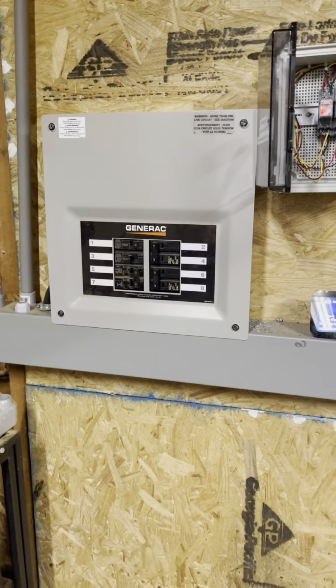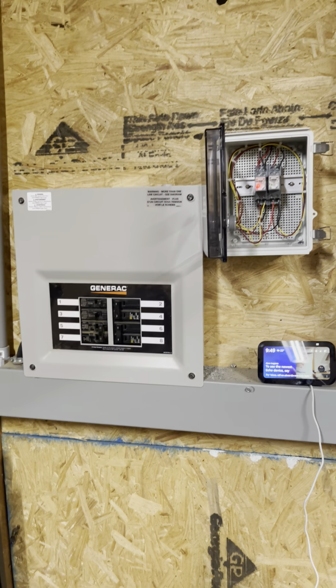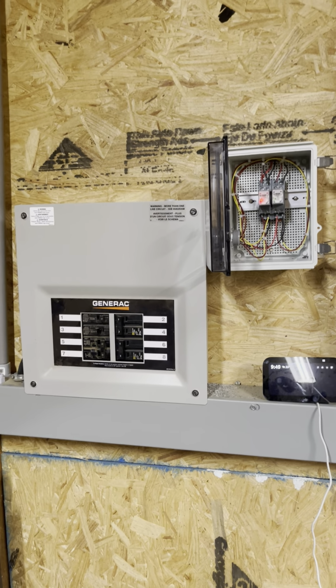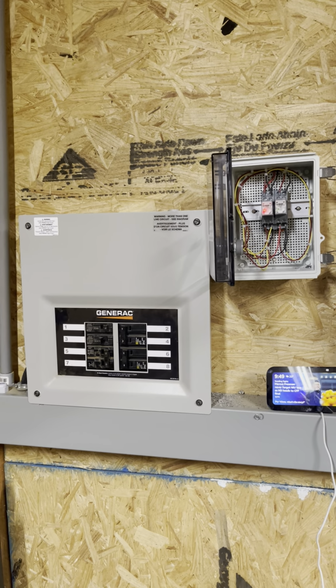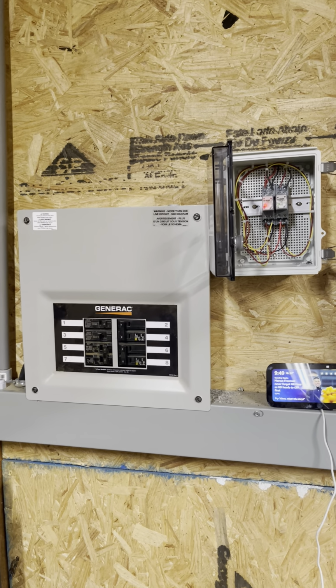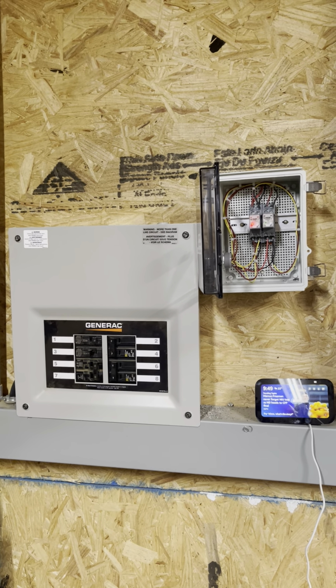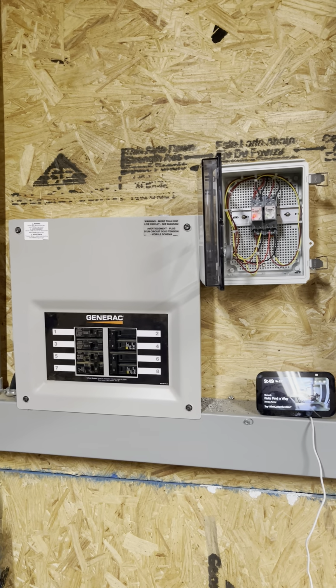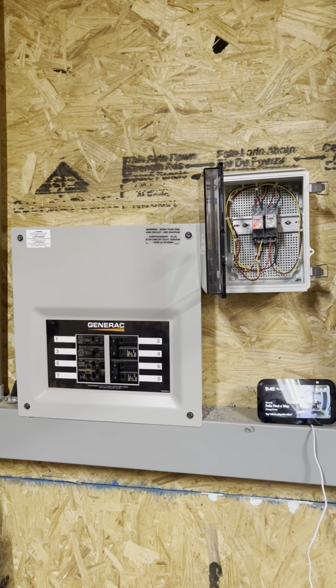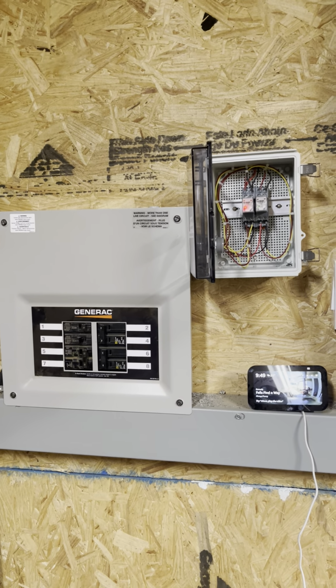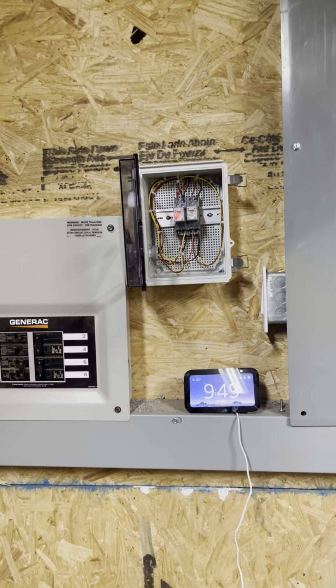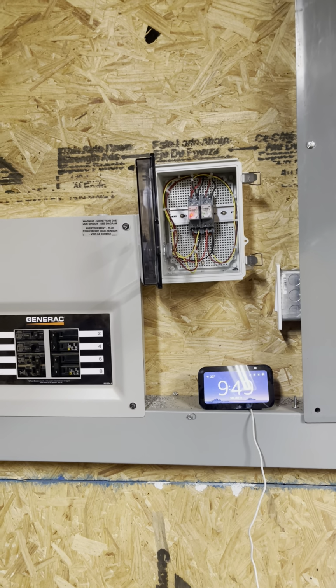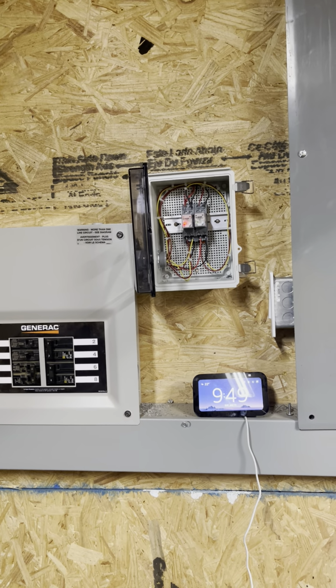Now I know that EG4 recommends that you have the same amount of generator power as you do wattage for feeds. One of the reasons I have 18,000 watts is for peak, and I run my shop off of it as well. In the case where my shop isn't on during the day, and if I was without power, I wouldn't run my shop. So when sizing my generator, the thing I looked at was this. If I bought a 20 plus kW generator and it was running at 50% load, it's going to burn somewhere around 3 to 4 gallons of propane an hour.